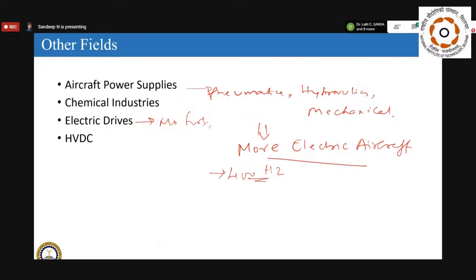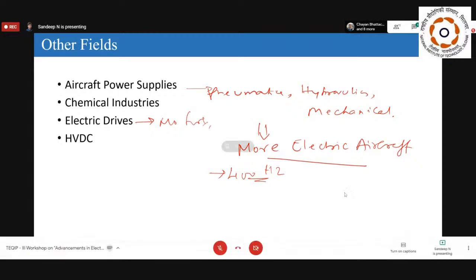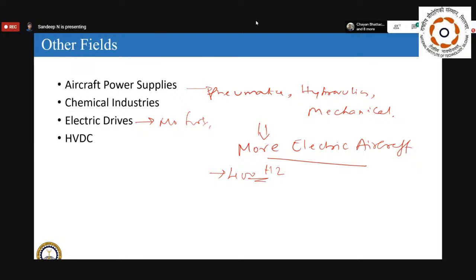Then we have the HVDC application. The idea is to generate high voltage DC and transmit it over the lines. The advantage is that two systems at different frequencies can be coupled through an HVDC link - there is no frequency constraint. As I told previously, the transmission line is basically R and L, so once we have DC on the line, there is no L impact, and no reactance losses, since it is DC.